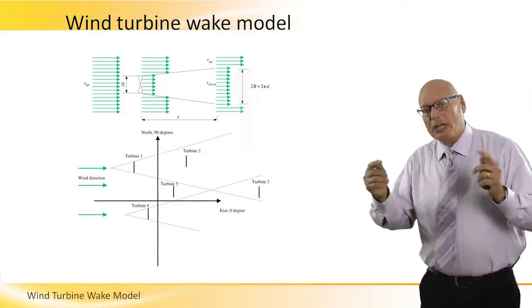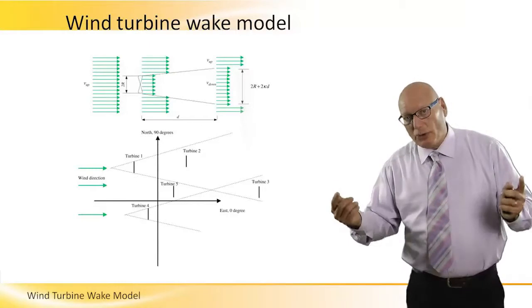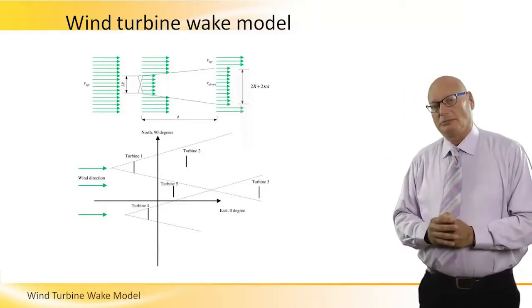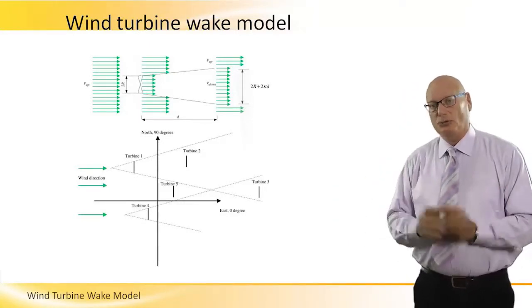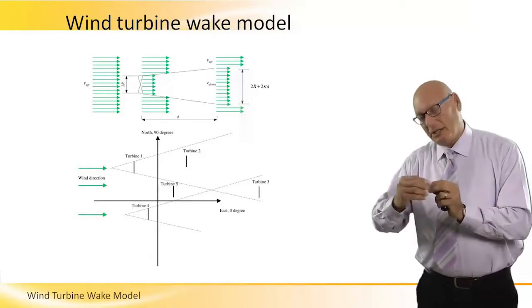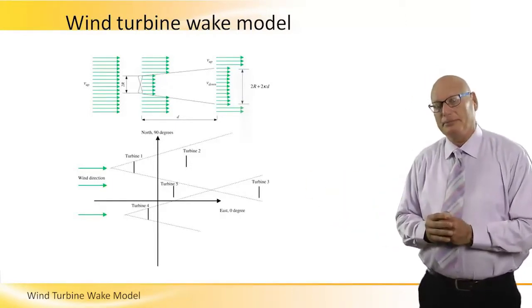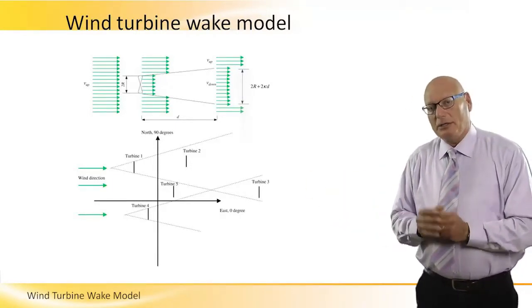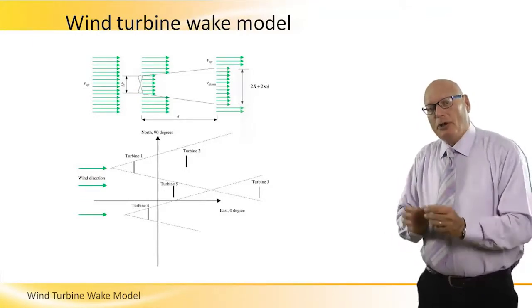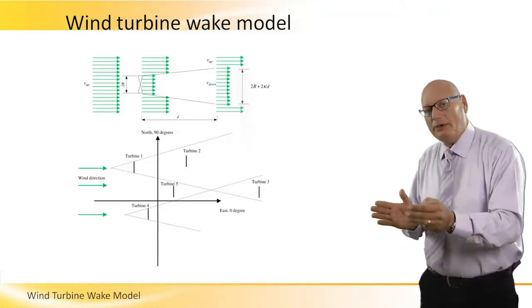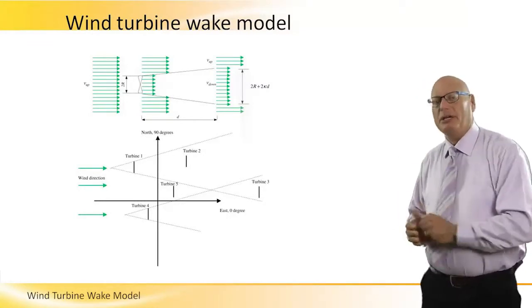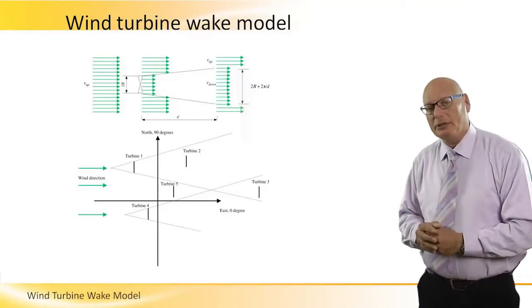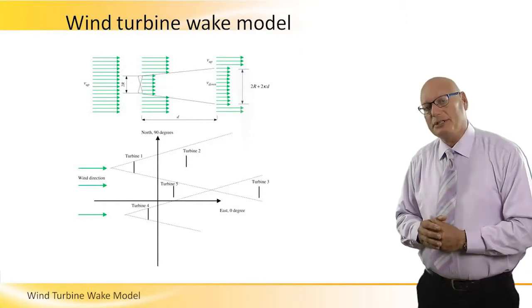And if we have a rotor diameter of about 200 meters, meaning the length of a blade will be 100 meters, in this particular example we need to keep one kilometer away from one turbine in the front row to the one behind it. And one kilometer is a very long distance.